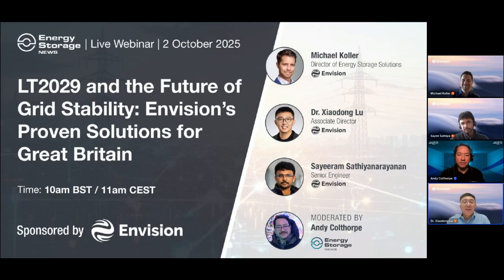Yes. The response time of inertia or reactive current of the grid forming BESS is instantaneous. There's also a specification from the NESO that when they certify grid forming performance, they require the response time to be less than 5 milliseconds. We had a workshop with them and asked the reason behind it. The answer is because it's a mimic of the virtual synchronous generator. You should have instantaneous behavior on the reactive current or active current injection into the grid when grid events happen. So we put 5 milliseconds there to make sure your response is instantaneous, because 5 milliseconds means you don't have enough time for the detection.